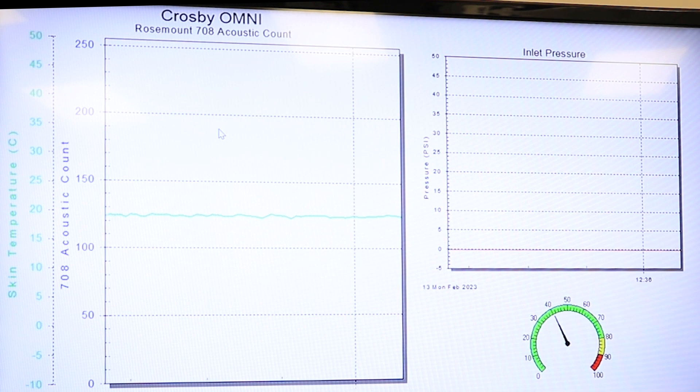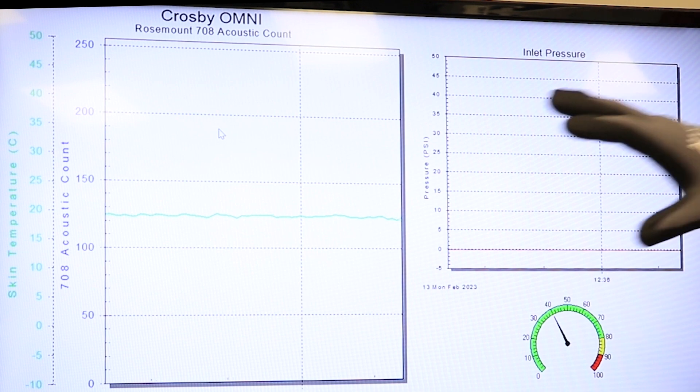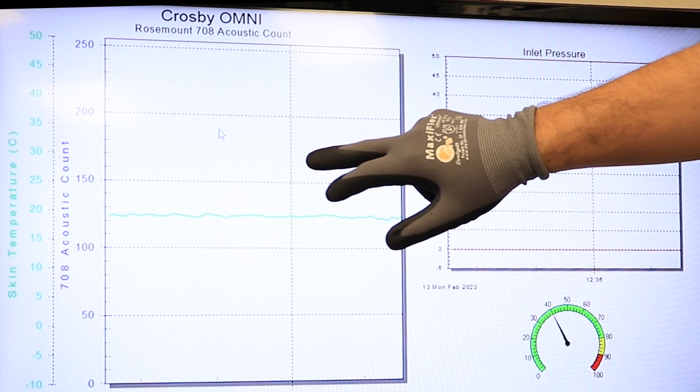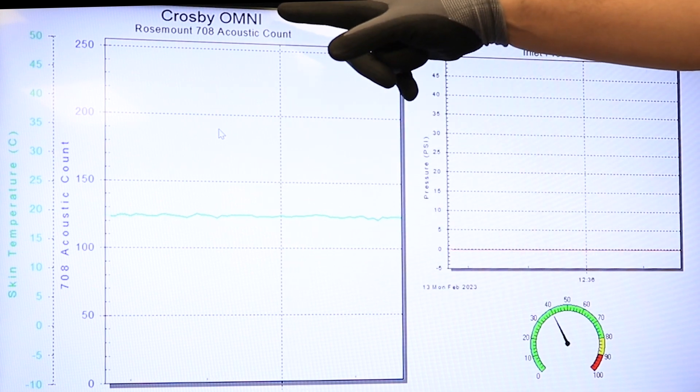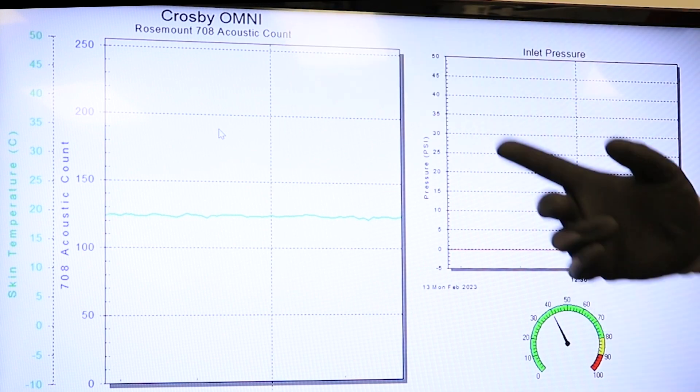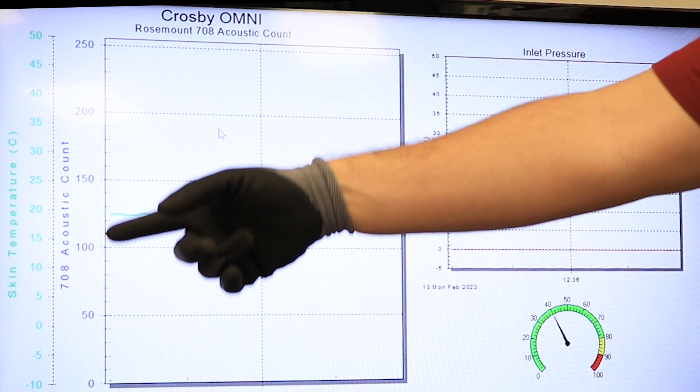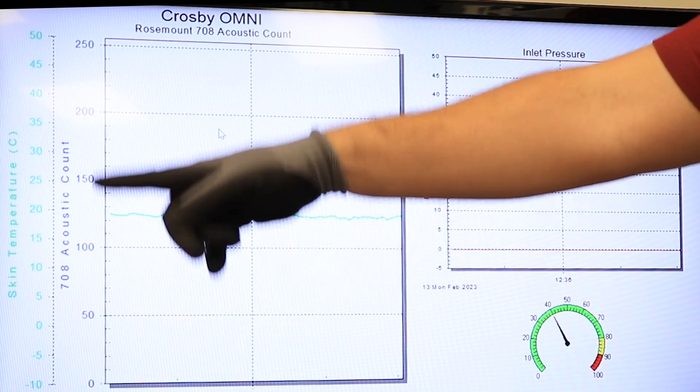In this graph, we're graphing the system pressure with a different pressure transmitter that's not part of our solution. We're also graphing the pressure at the inlet of the Omni PRV. But more importantly, we're graphing the two variables from the 708 mounted at the outlet piping of the Omni. The first one, in blue, we're graphing the acoustic counts that go from 0 to 150.